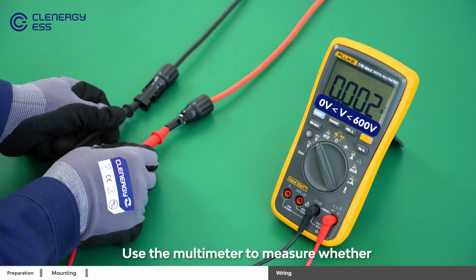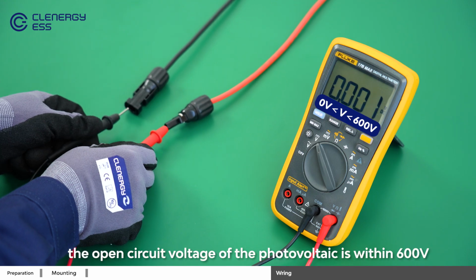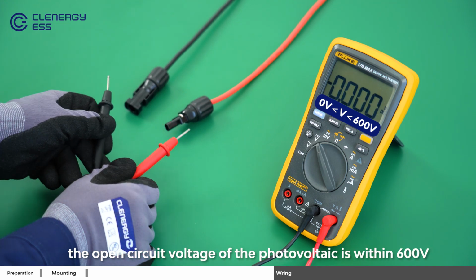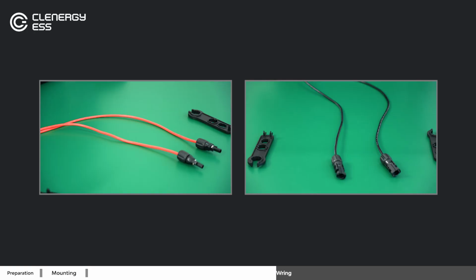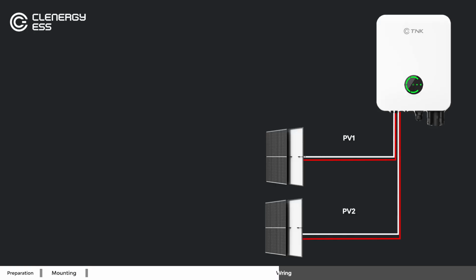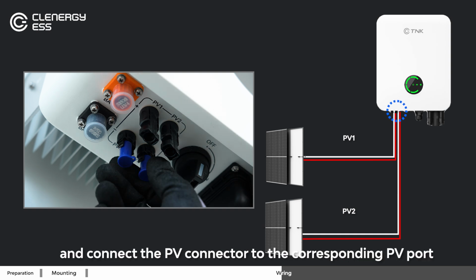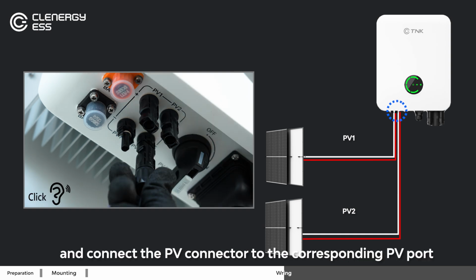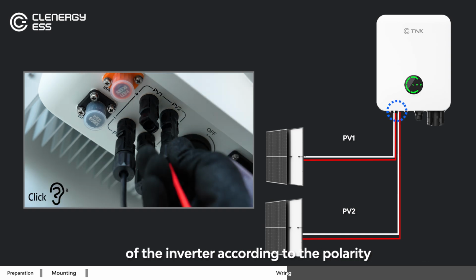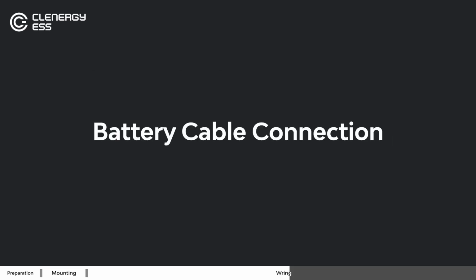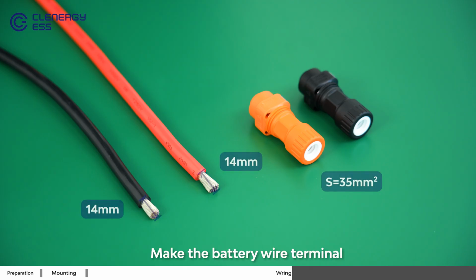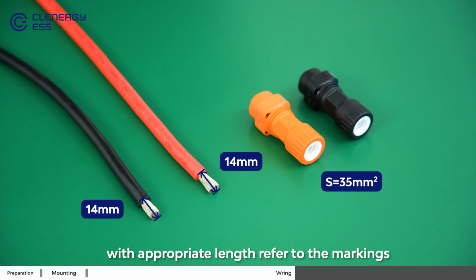Use the multimeter to measure whether the open circuit voltage of the photovoltaic is within 600 volts. Remove the waterproof plug and connect the PV connector to the corresponding PV port of the inverter according to the polarity. Battery cable connection. Make the battery wire terminal with appropriate length.